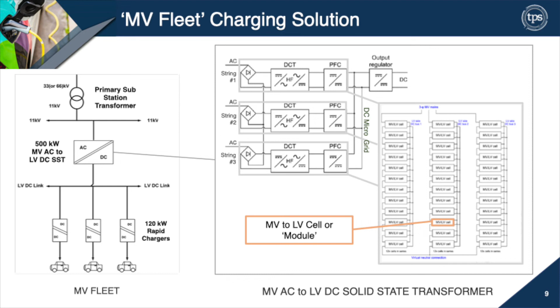Here's the MV to LV module. Here's the critical bit. Now, we developed a module here that fits roughly in a shoebox. It's quite small. It needs to be compact. It's 15 kilowatts. It's 98.7% efficient. The magic number is 99%, and there is a route map to that. The high-frequency transformer can now switch at 230 kilohertz. That's what silicon carbide does for us. So it's got a very unique transformer in it to enable us to switch at those frequencies. And we've got 12 modules per string, giving us N-1 redundancy. And using that, we can get to a 500 kilowatt solid-state transformer.